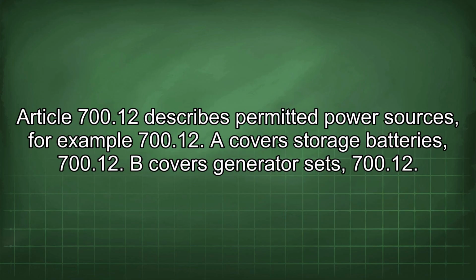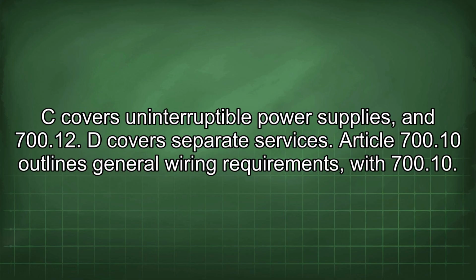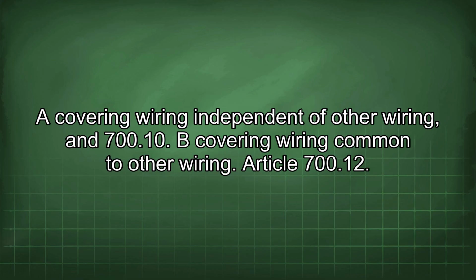Article 700.12 describes permitted power sources, for example, 700.12(A) covers storage batteries, 700.12(B) covers generator sets, 700.12(C) covers uninterruptible power supplies, and 700.12(D) covers separate services. Article 700.10 outlines general wiring requirements, with 700.10(A) covering wiring independent of other wiring, and 700.10(B) covering wiring common to other wiring.